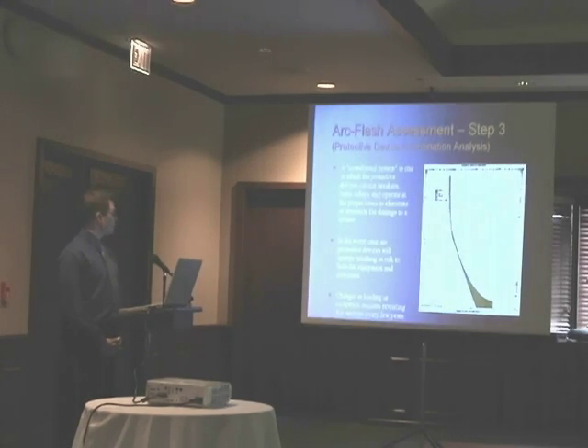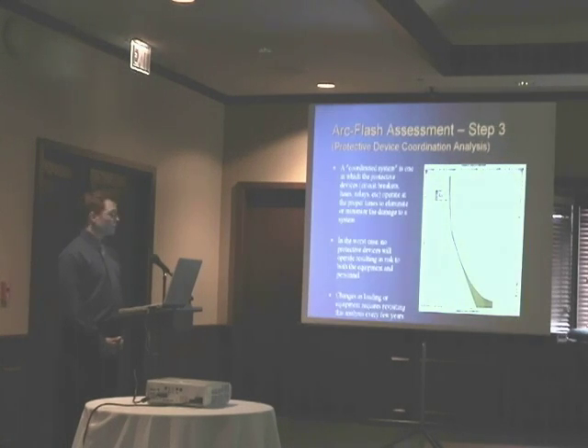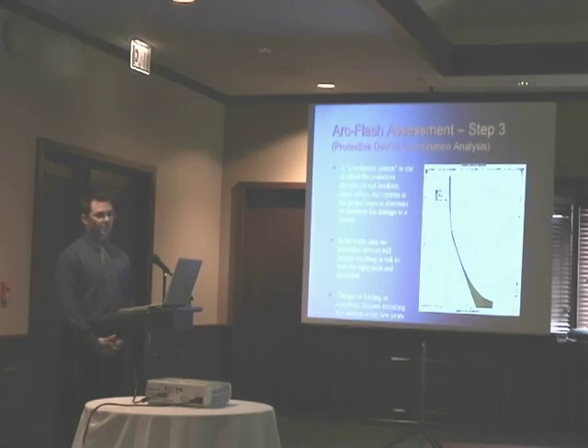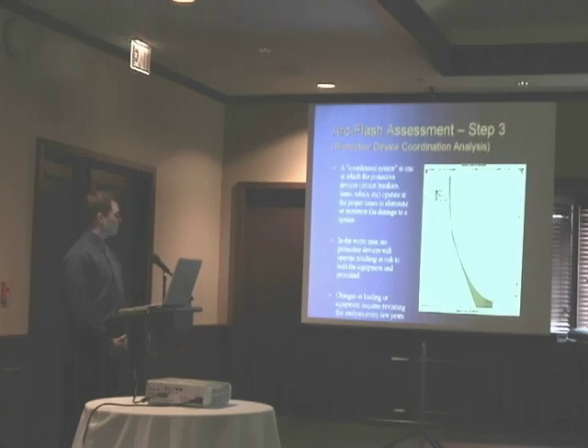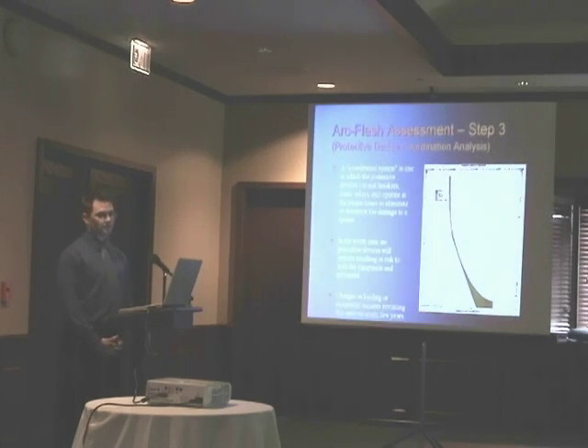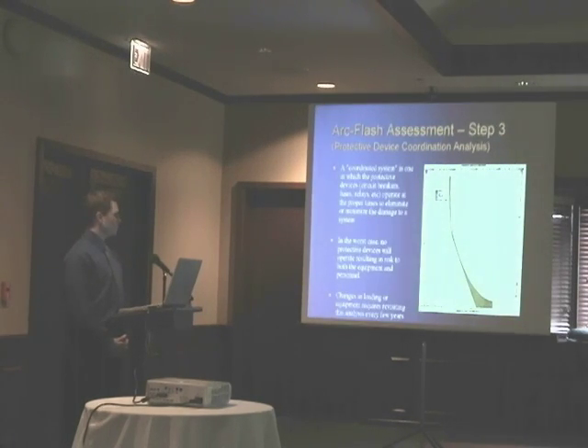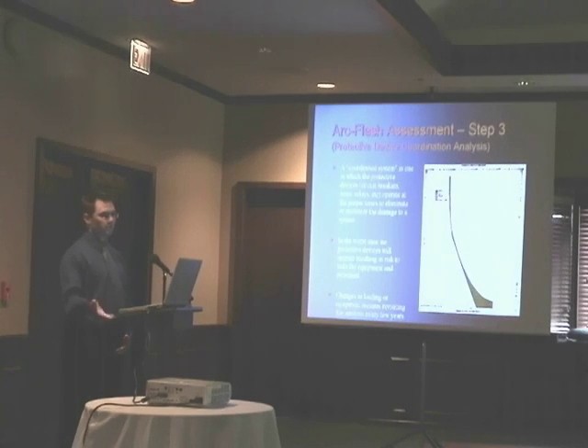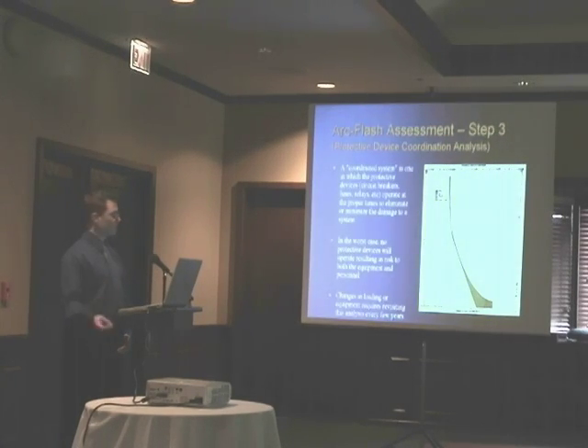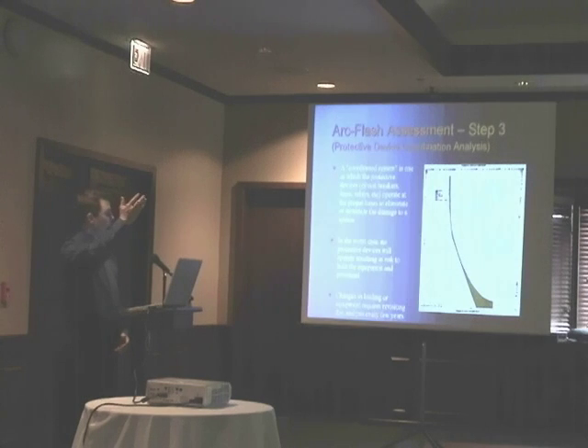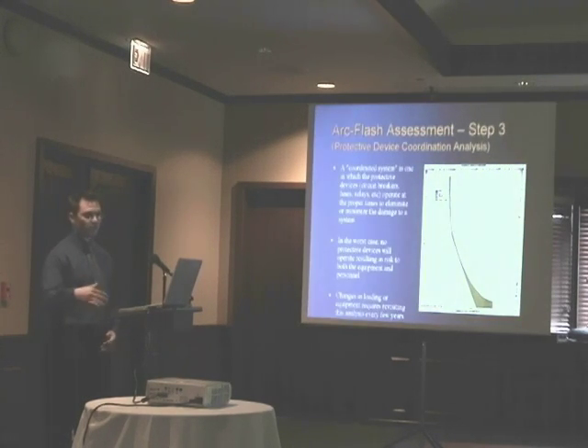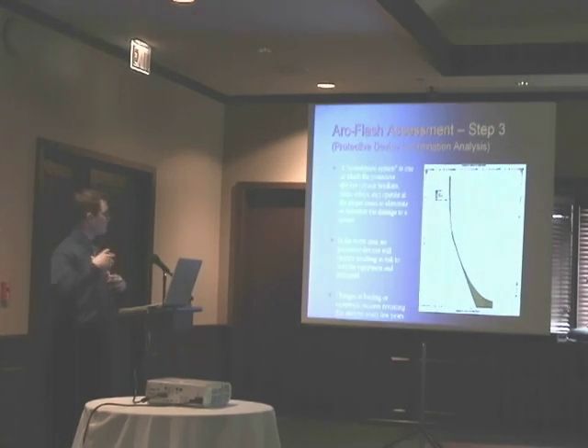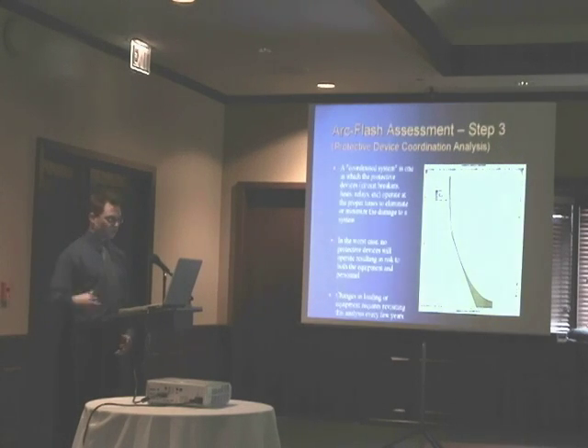So basically, you want to go in for a protective device coordination analysis, and you want to operate from a ground up way. You want to start with your motors, or your lowest protective device on that motor, and work your way back to the utility. The OCPDs should operate from there up if an arc flash happens. This one should go first, and as you get higher, they should trip to cause less of an arc flash.